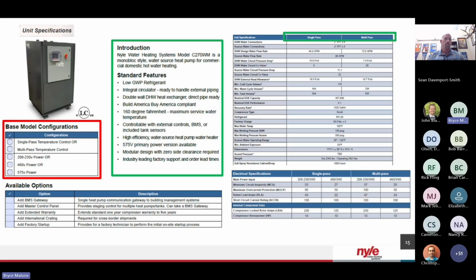And the differences in this case depict the flow rate differences, because as you can see, if I pipe something in single pass with a C270, I'm going to get 44 gallons a minute. Whereas if I pipe it in multi-pass, I'm going to give you almost double that, so 72 gallons. And this boils down to when do you use one over the other.